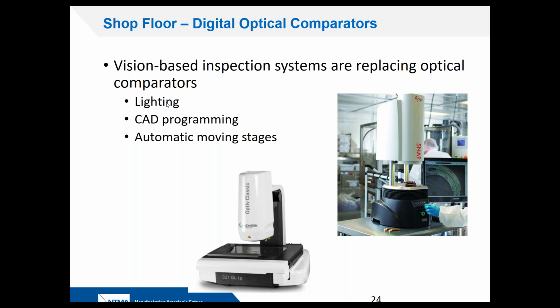So manufacturers have gotten better at getting repeatable lighting, creative lighting, which I'll show some in a minute. There's also CAD programming, being able to load in a 2D CAD file and set up your measurement requirements off of it, making these more useful for measuring out on the shop floor, partly because a lot of that programming can now be done in advance. It can be done in the office, and then you can send the program to the machine so that a machinist can take a part out, put it under the machine, measure, and get a determination on the shop floor, either for 100% inspection or at least for measuring criticals to avoid large batches that have to be scrapped.